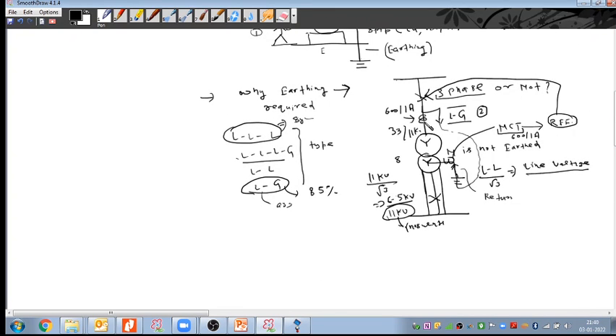You mentioned the neutral CT, right? But you might have a core balance CT upstream. You usually have a core balance CT on the upstream, and if you have a core balance CT which is doing this unbalance detection and you have a return path, the core balance CT can detect it. What you said is correct. I'm just adding a point: in the systems I worked on, we have a core balance CT fitted there for the upstream.